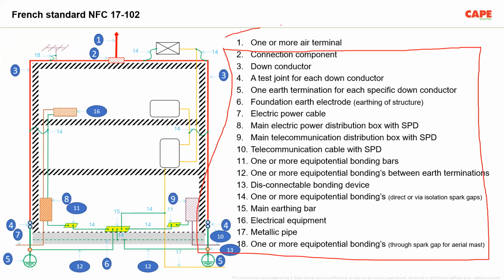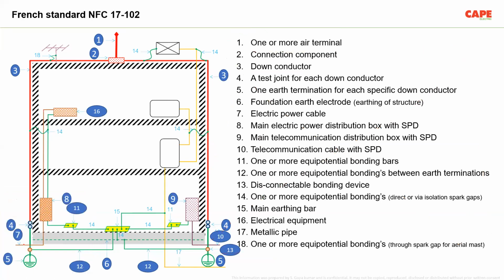So item number 1 is not mandatory, or not required, as per the IEC standard. The French standard says you need 1 to 18. So technically, by making this item number 2 to 18, your building is actually satisfied. As per the requirements of 62305, your requirement is satisfied by serial number 2 to 18. But what the French standard says is, you put an additional rod here. One more, you put an additional rod. This rod is an additional.